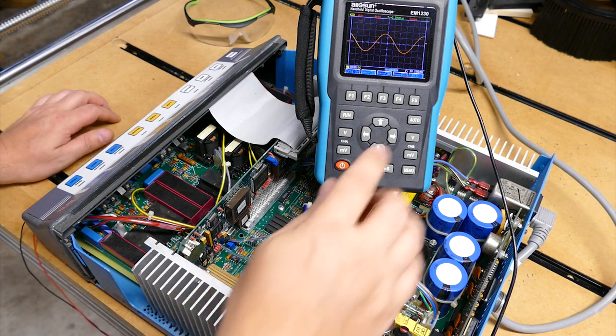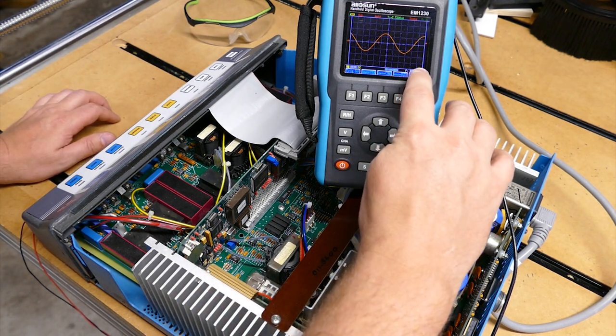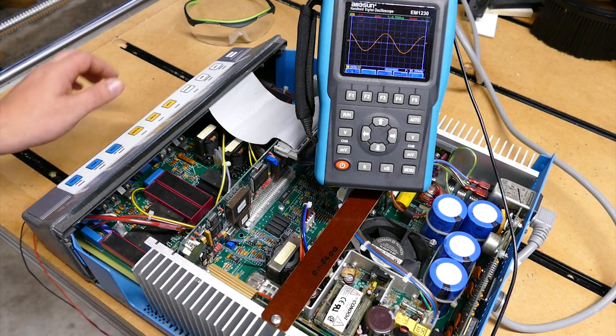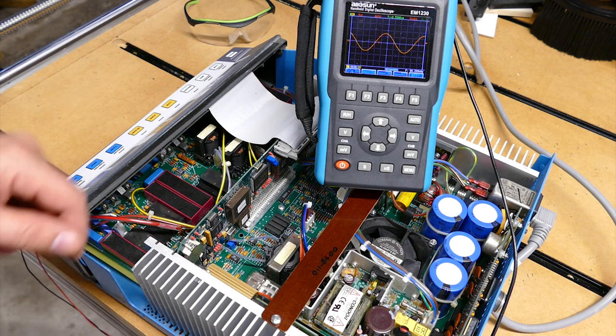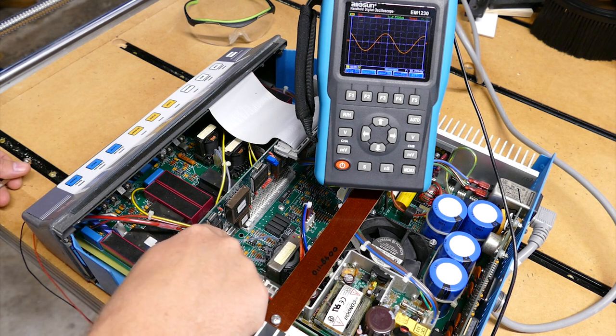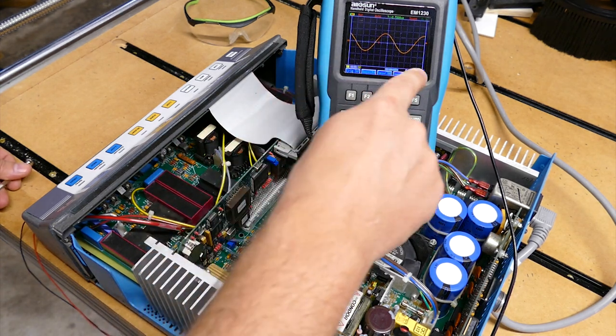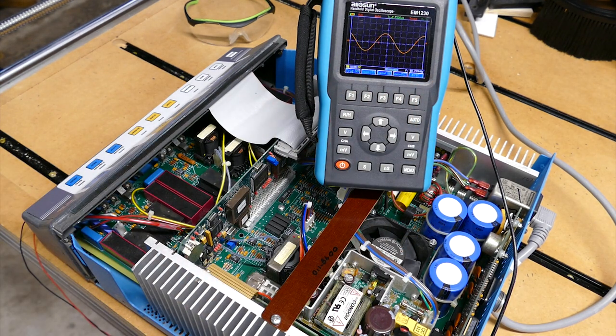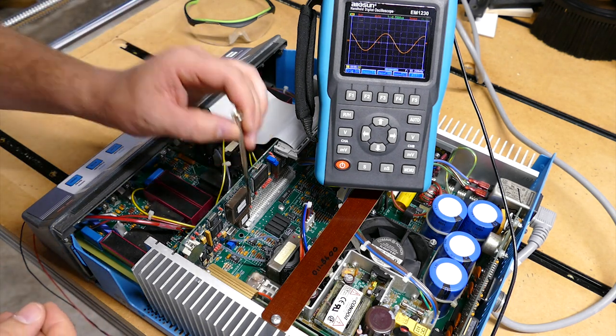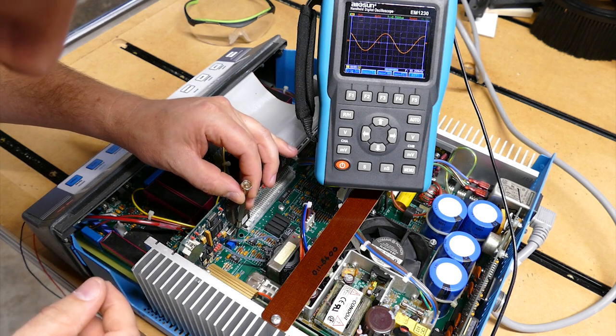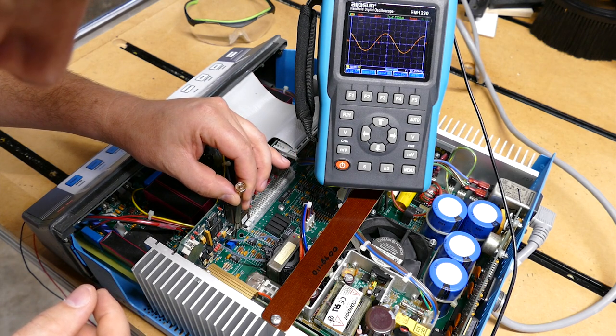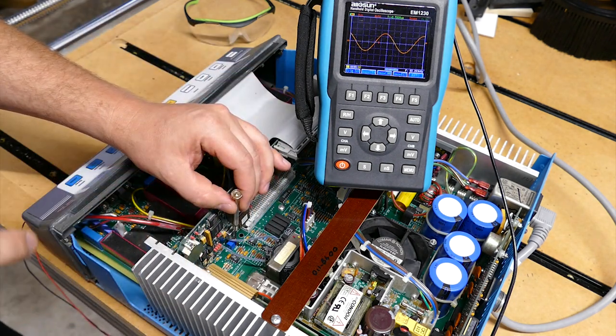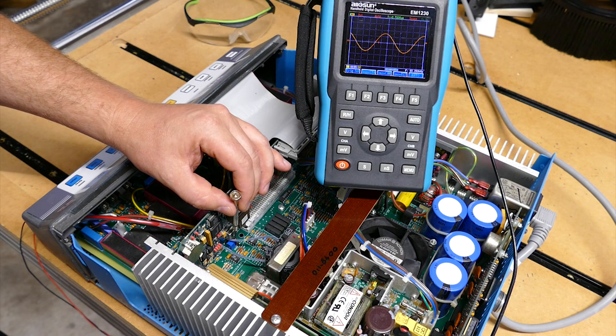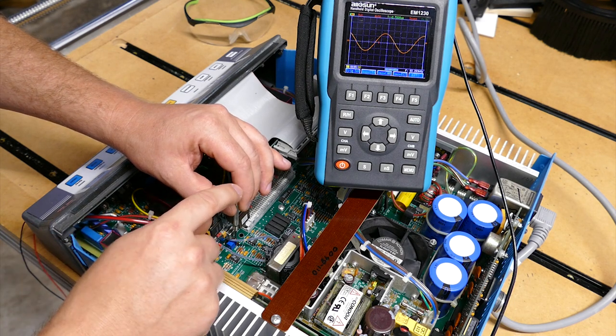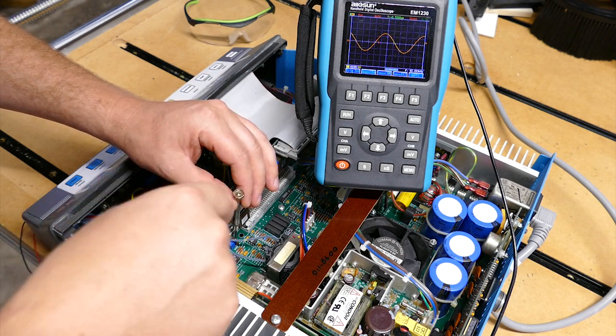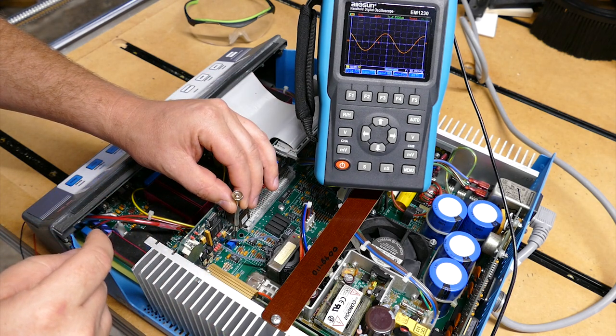I don't know if you can see it too clearly on the video, but right over here is my frequency of the waveform. It's currently at 80.25, and you can see I've got a clear signal. And what they request us to do is to adjust this little resistor down here, this potentiometer, and the frequency should read roughly 82 kilohertz. So in order to do that, we are currently in OP mode. I'm going to stick my flathead screwdriver down on it. Be careful not to put any pressure down on the screw, because putting pressure down on a potentiometer will change the value to a superficial level. So I'm currently on the screw, barely pressing down at all, and I'm gonna rotate that potentiometer.